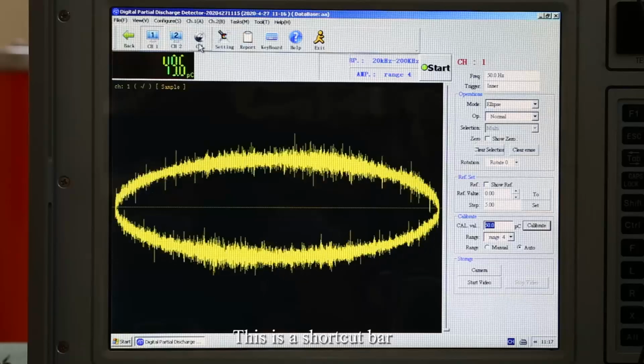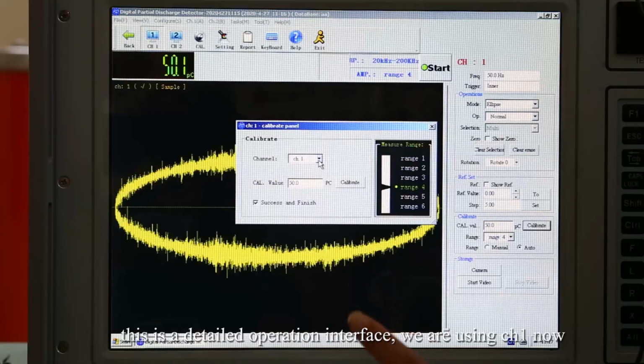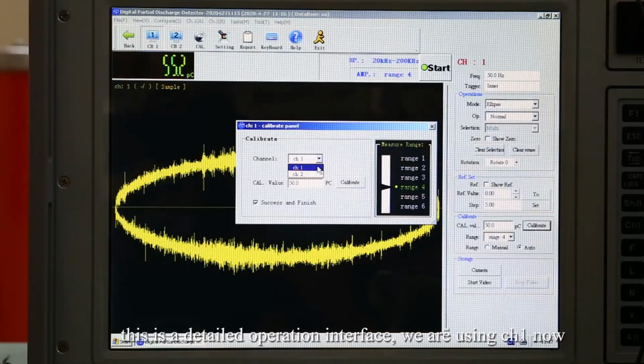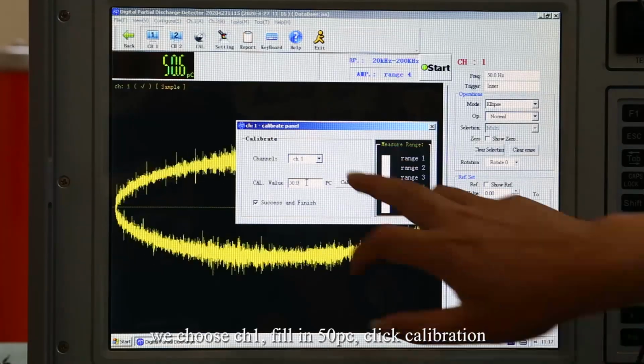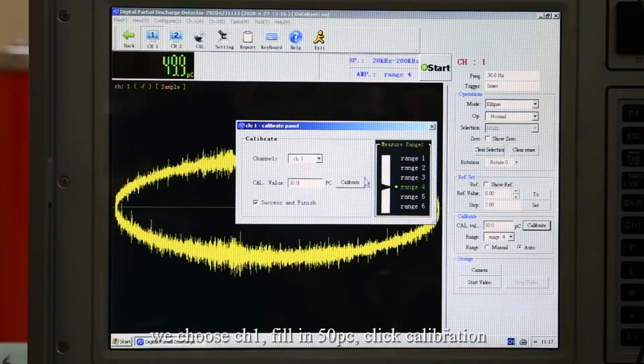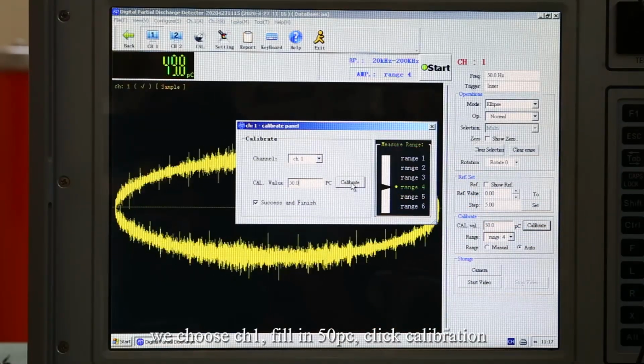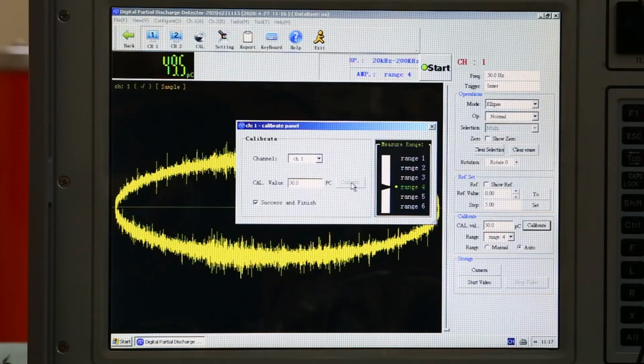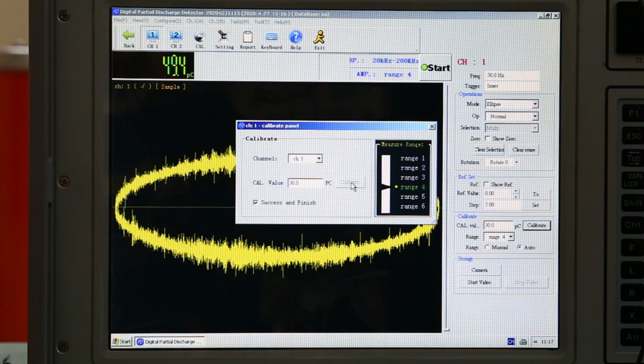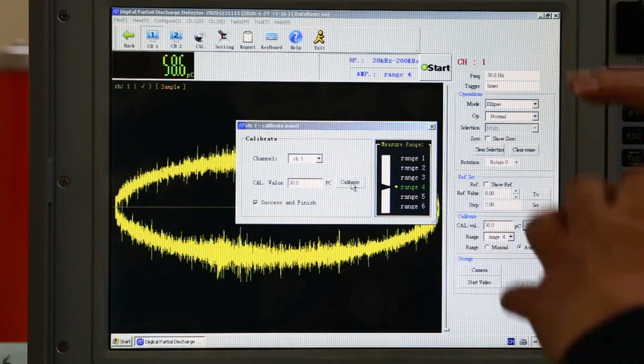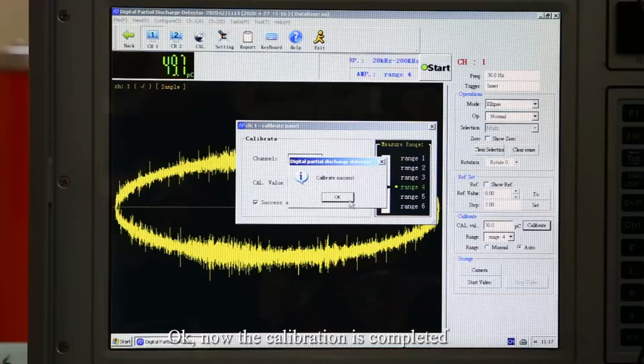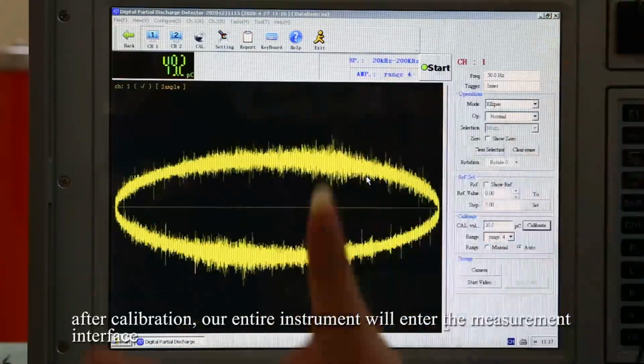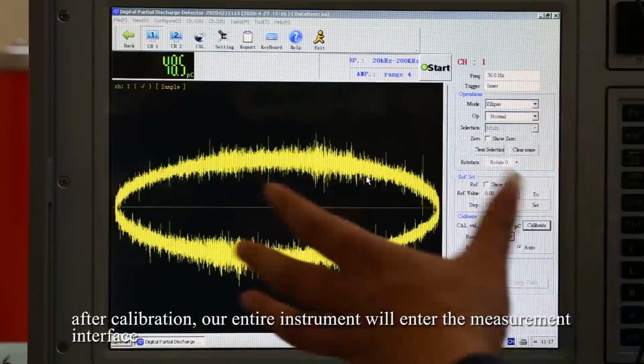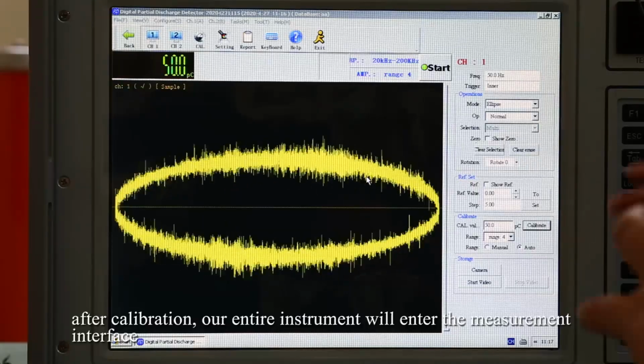This is the shortcut bar. This is the detailed operation interface. We are using CH1 now. We choose CH1, fill in 50PC, click calibration. Okay, now the calibration is completed. After calibration, our entire instrument will enter the measurement interface.